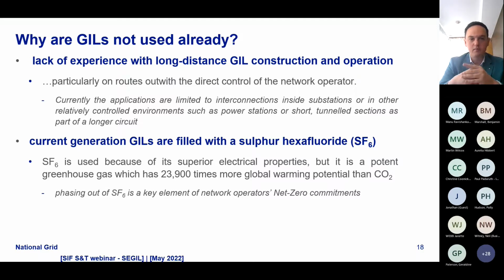The other problem, which might be even bigger, is that the current generation of GIL are filled with SF6, either pure SF6 or a mixture of SF6 with other gases. That's obviously not accepted anymore, to introduce more SF6 into the system. That's why in our project, on one side, we're trying to design GIL for longer distance transmission, optimized for bigger, longer transmission as well as lower maintenance. On the other side, we're looking at how we can replace SF6 in these pipelines.